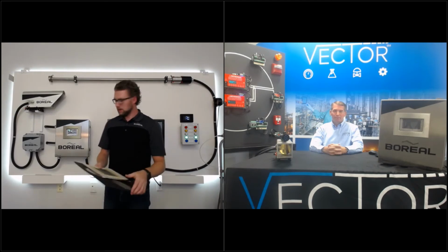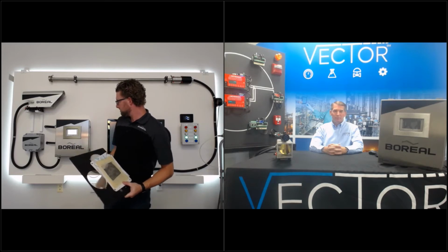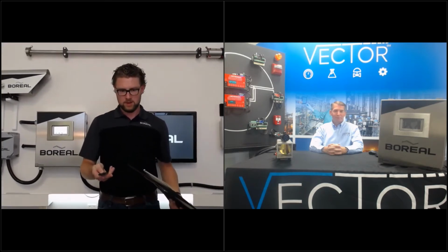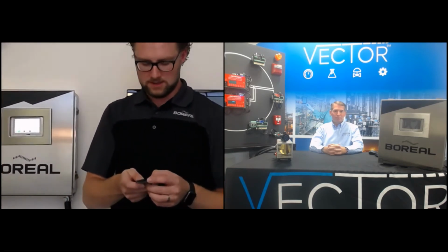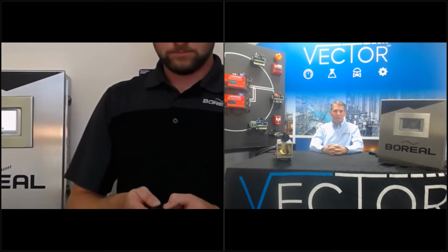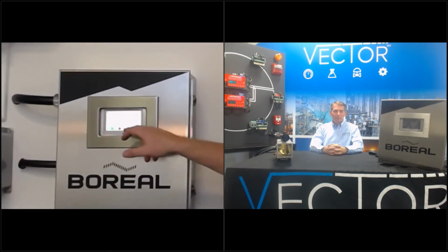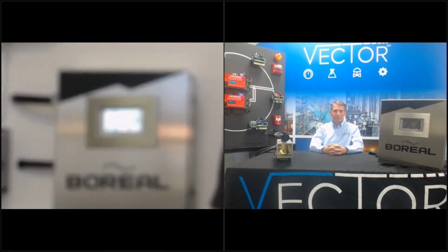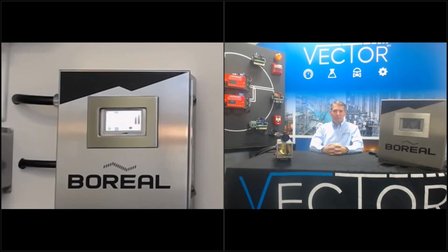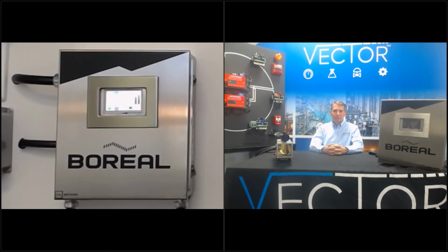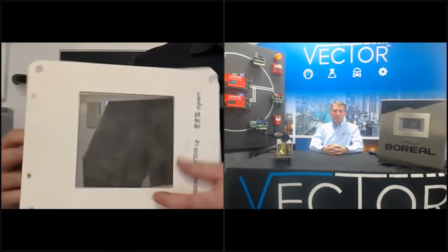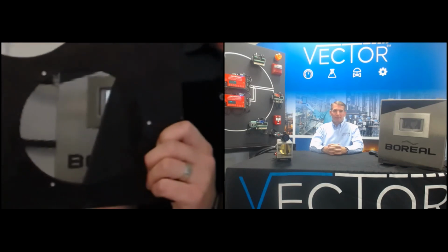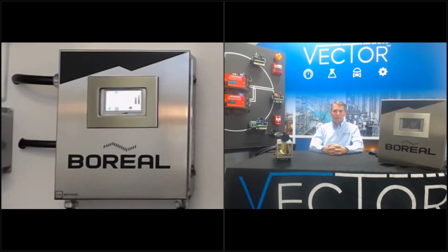So how the system functions and performs: this is an optically based instrument, as I think all of you have realized by now. There's a certain amount of laser light that comes into the path and a certain amount that goes out. In between the open path measurement head, there are certain functional tests for open path toxic gas detection that can be done. We can use screens or meshes to replicate different opacity levels, just like we have here. Part of the functional test for this particular technology and product is to show how much transmittance this system can handle.